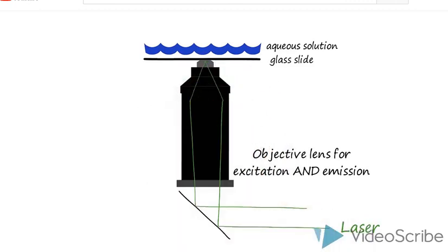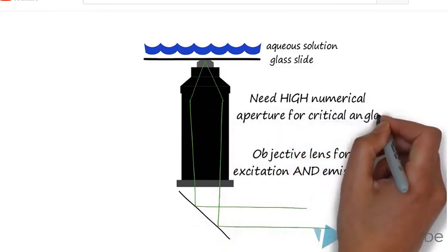Excitation light enters the objective lens off-center so that it can be sent at an angle to hit the glass-water interface. Because the critical angle of glass and water must be exceeded, O-TIRF only works if the lens has a high numerical aperture of at least 1.34.